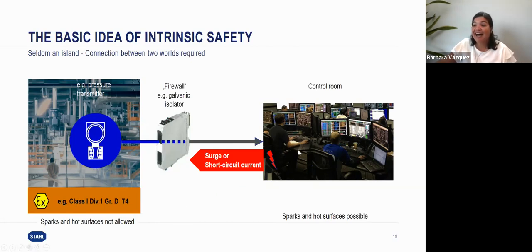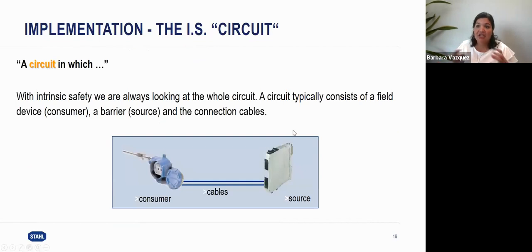It's a barrier. If we have high energy, it will not let it pass. So that's why we need the intrinsically safe field device and the barrier. Let's say it one more time. An intrinsically safe circuit is formed by an intrinsically safe field device, an intrinsically safe barrier, and the wires in between. So intrinsic safety should always be seen as a system protection method. We need the three of them working together to create an intrinsically safe loop. And this loop will be so safe that if someone breaks the wire, does a short circuit, or you have an open circuit, and a spark happens, that spark will never be hot enough to react with the explosive atmosphere. That's why the three of them need to work together.